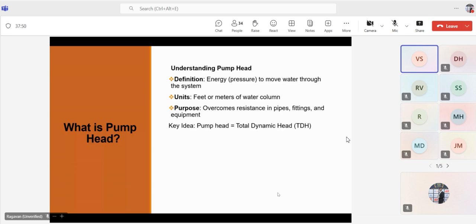In HVAC applications like a chilled water system, the pump head is critical for ensuring the chilled water circulates effectively through the cooling system, including the pipes, coils, and fittings.